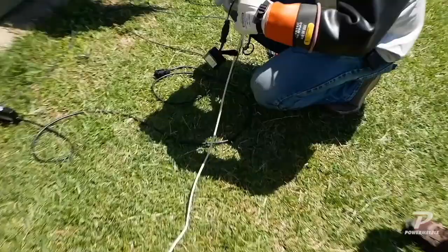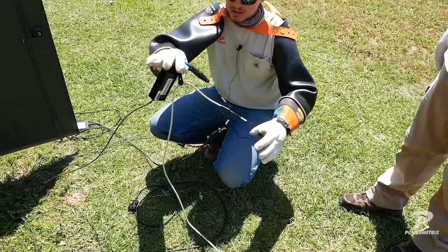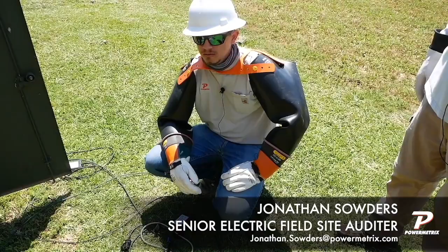What I did was first change the CT that was on C phase and put it on B. That ruled out the flex ring. Then, instead of being on the yellow on the extension cable, I switched over to blue. I changed it here and changed it back there where it ties into the normal probe adapter cable. Now, since we've ruled out the CT and ruled out the extension, there's only one more to go.